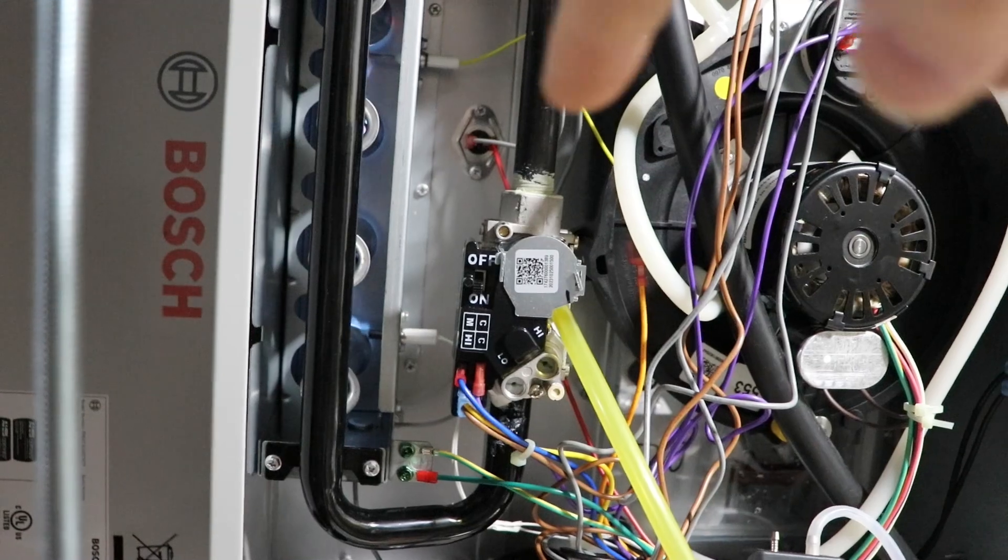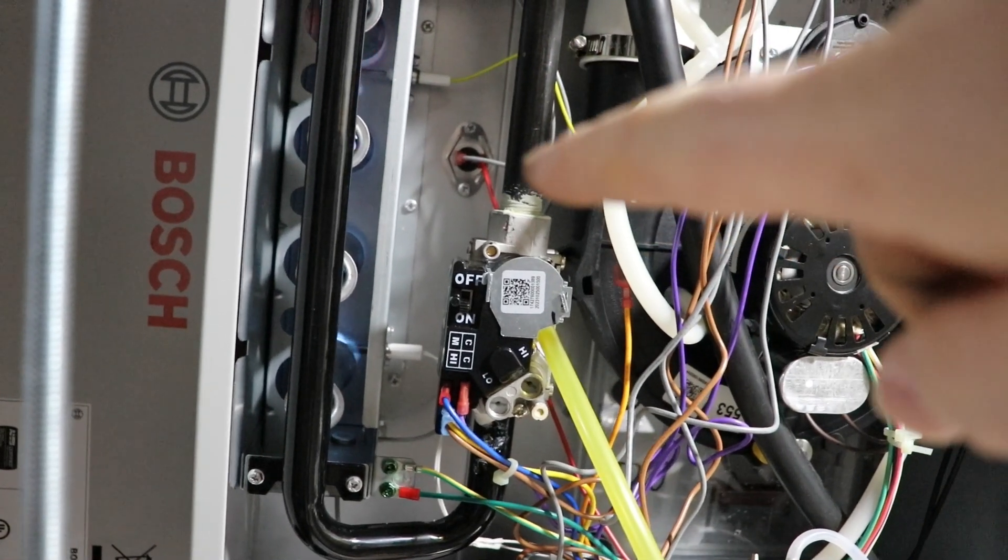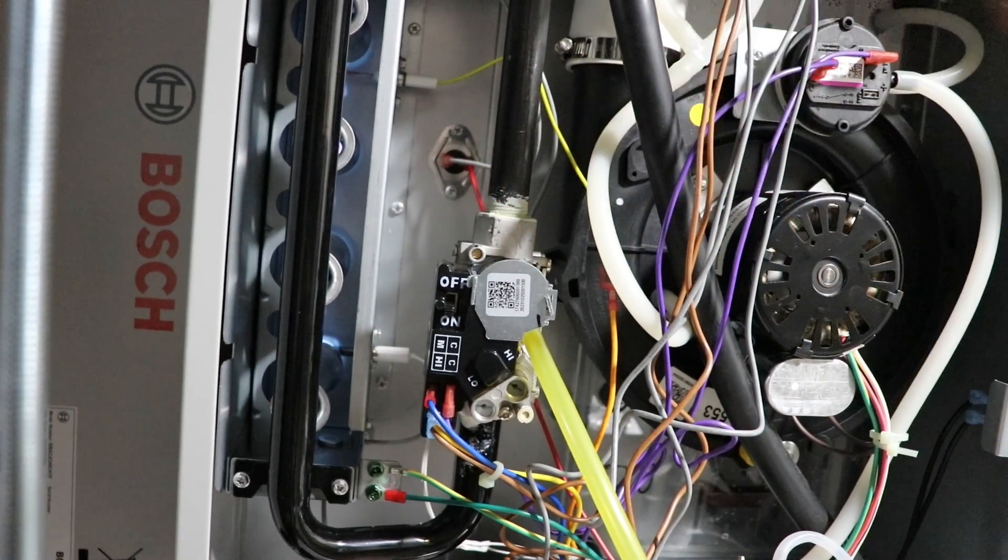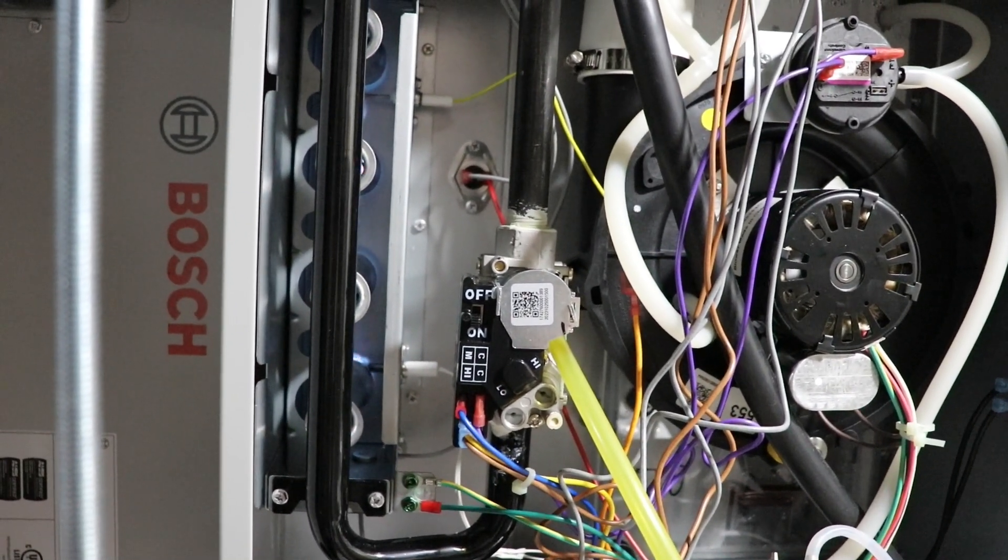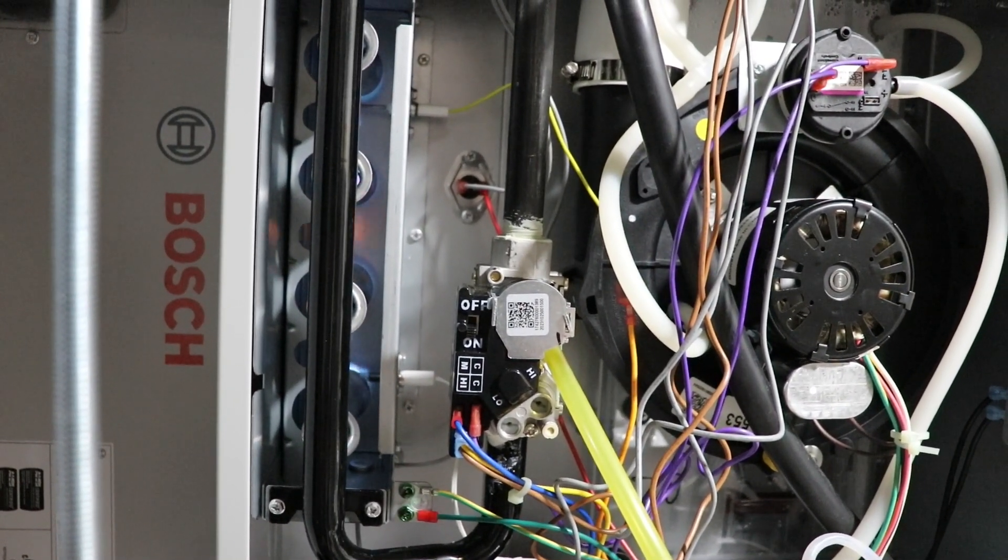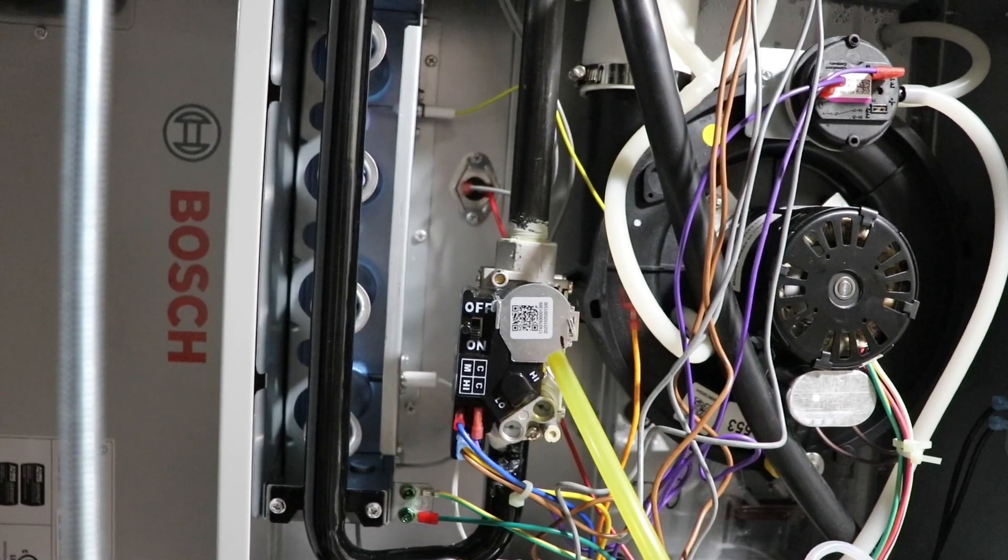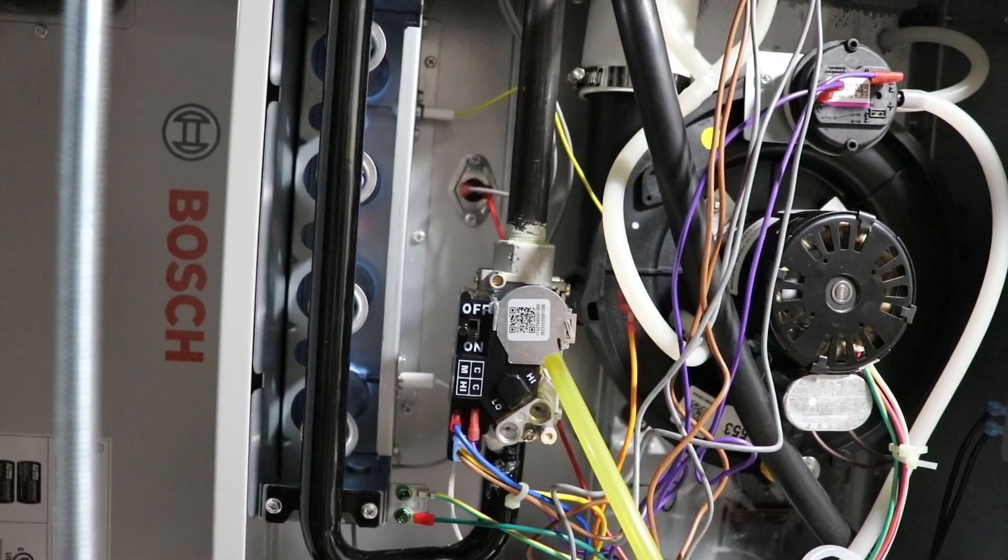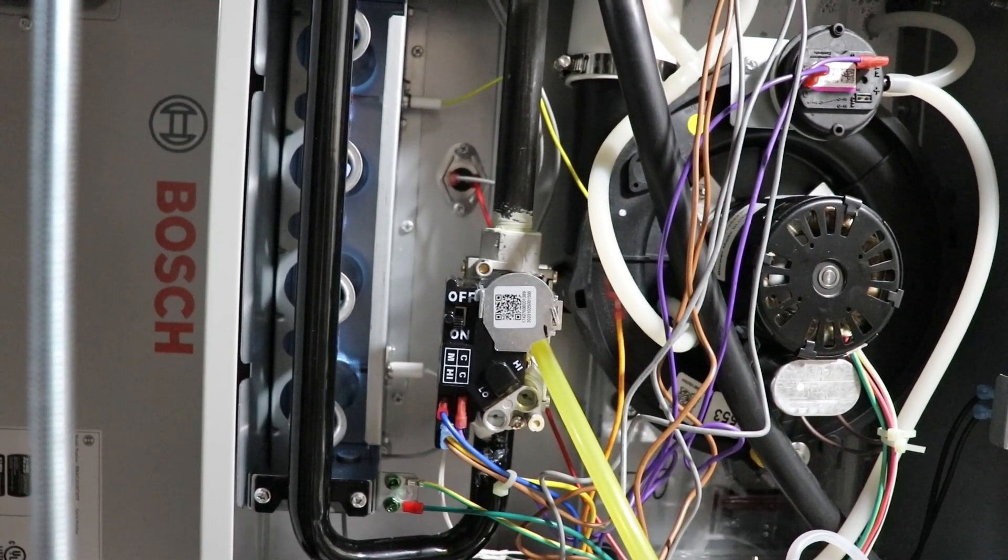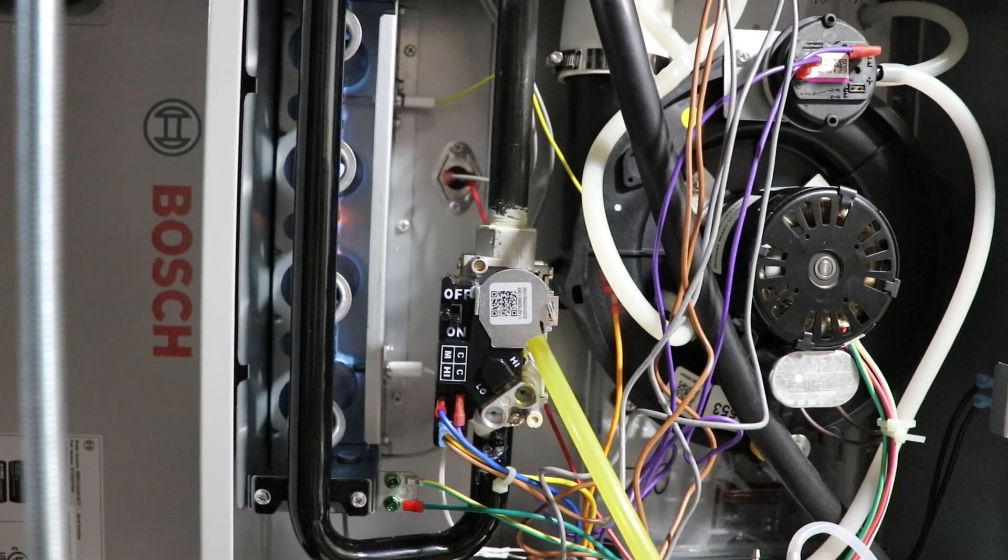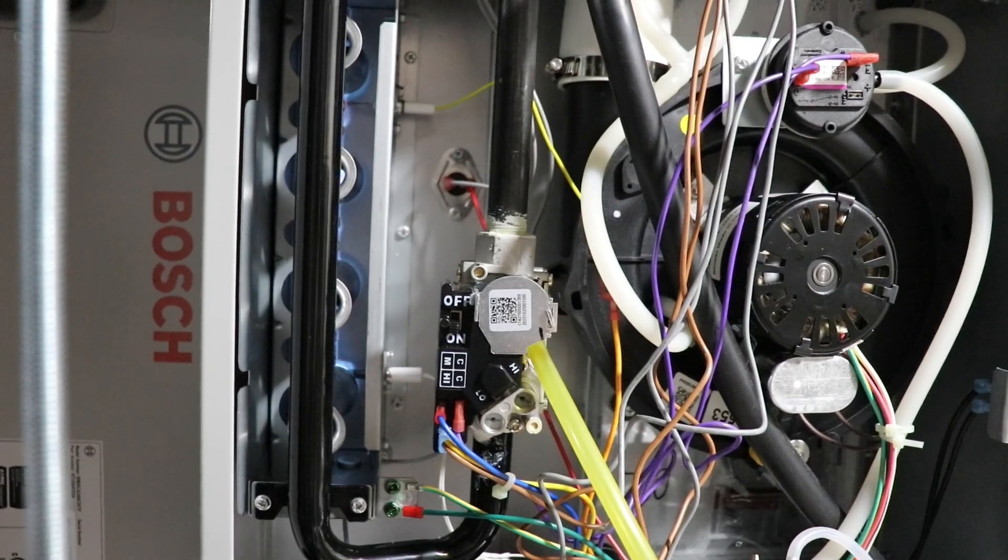Right here, it's basically that dude there is telling the furnace that the heat exchanger is getting too hot, which is true, but it appears to be that it's because of over firing.